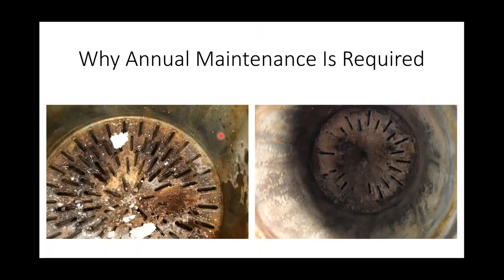So why is annual maintenance required? Well, as with fire tubes, as you can see in here, this has a little bit of refractory that fell down on it. This one was never serviced. As you can see, the tubes basically just sealed themselves up. We want clean passageways. We want the flue gases to travel down through all these tubes and have a good exchange with the water that they're encased in. If there's a buildup of products of combustion, other debris, or anything they're sucking in from the air intake, it can create film on the tubes, which can result in overheating, which can result in warpage or further damage or possibly even leaking.